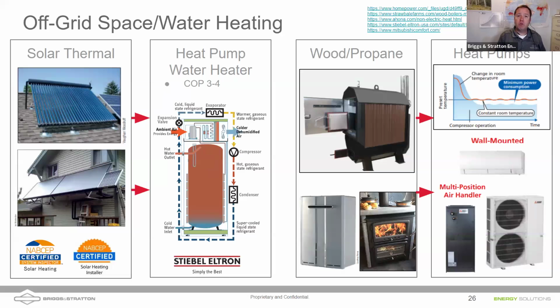Of course, we're still going to put in low battery voltage disconnects to take away the chore of a homeowner having to watch their app to see if batteries are getting low and adjust their behavior. But again, if we have a properly sized system and a generator able to start automatically using a 2-wire signal, an off-grid system really shouldn't need any load control.